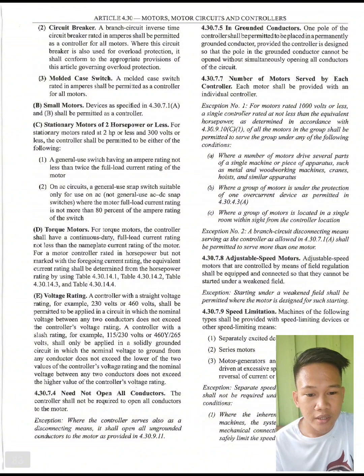Third, we have molded case switch. A molded case switch rated in amperes shall be permitted as a controller for all motors. B. Small motors. Devices as specified in 4.30.7.1a and b shall be permitted as a controller. C. Stationary motors of 2 horsepower or less. For stationary motors rated at 2 horsepower or less and 300 volts or less, the controller shall be permitted to be either of the following.